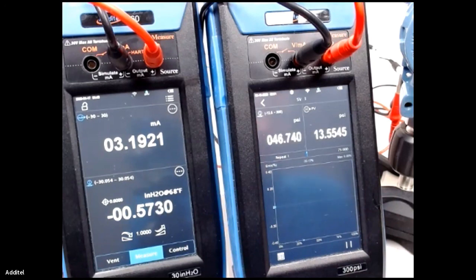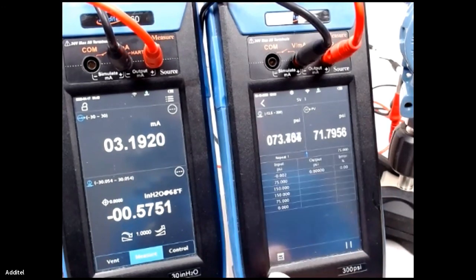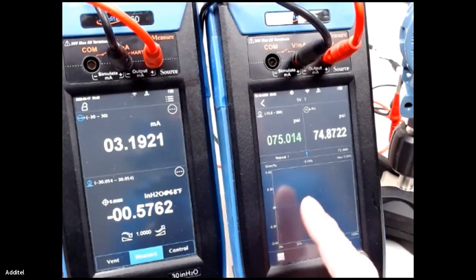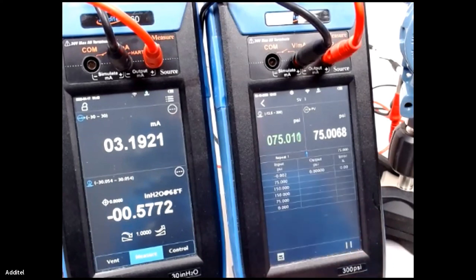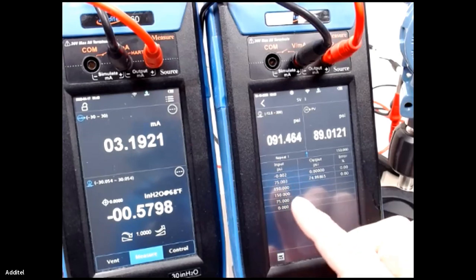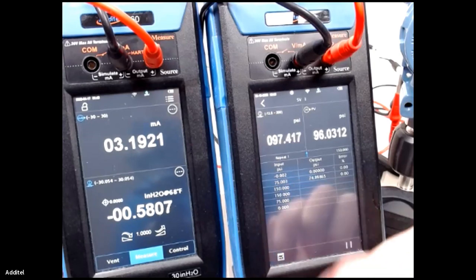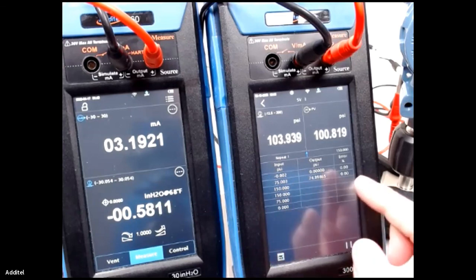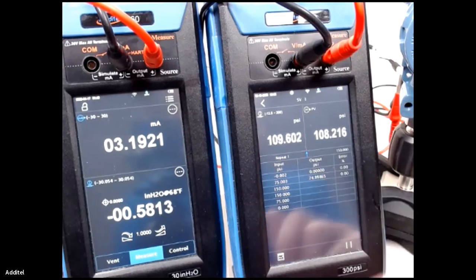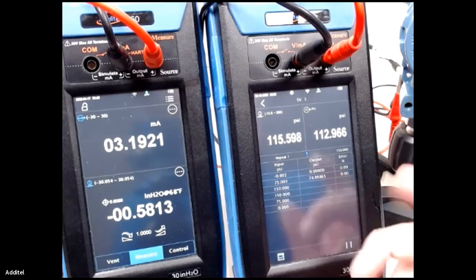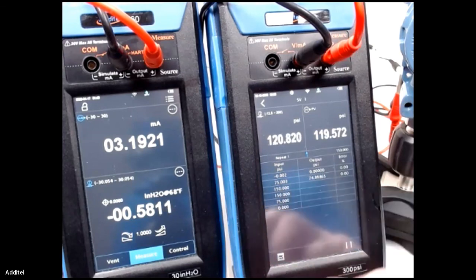So it did the first point, and now it's going up to the second point at 75. I'll show you, you can look at this in two ways: this graph feature we're looking at, or you can go look at the actual raw data at where it took the point. I don't know if you can see that last one, but we had it set at 75, and it took it at 74.998, so our error was literally nothing as far as it goes. There probably was a slight error, but within our tolerance, it didn't show up.